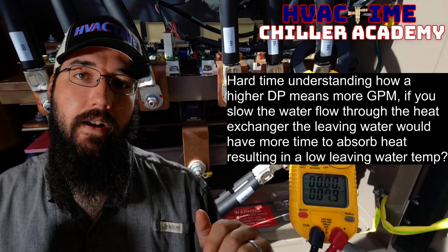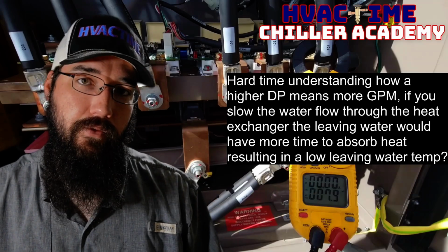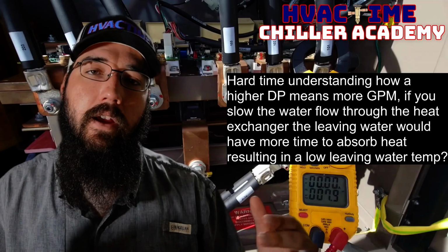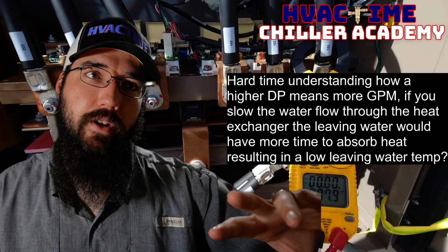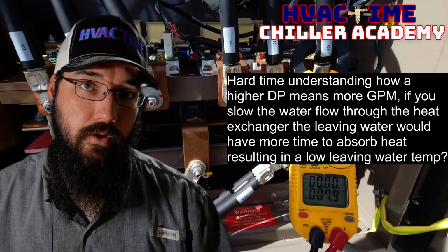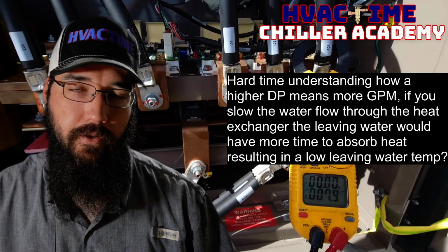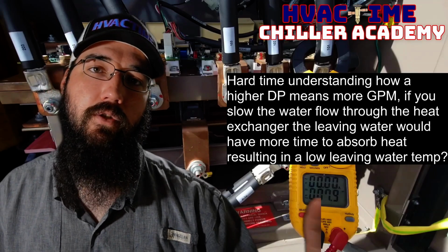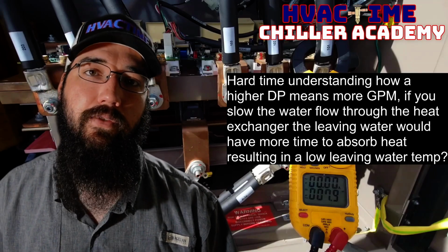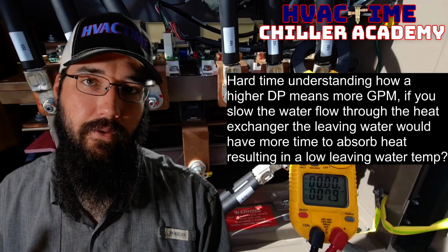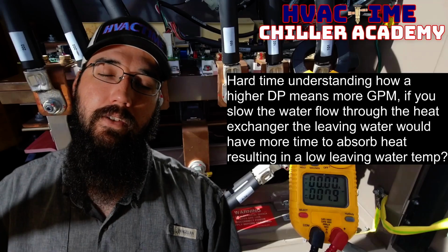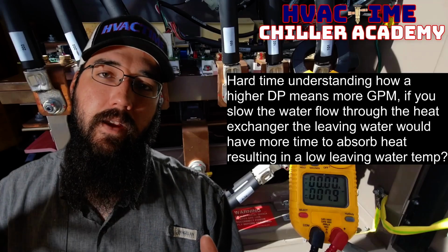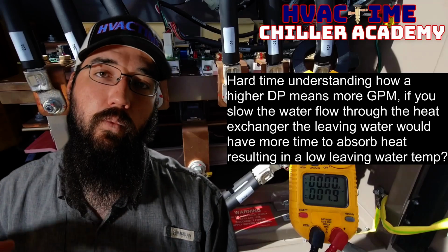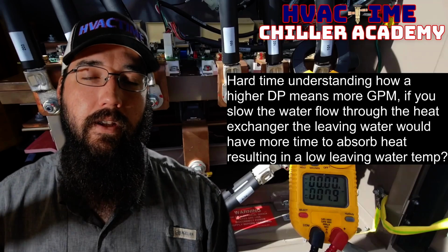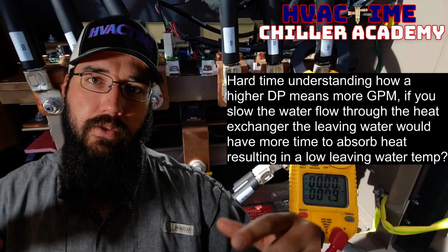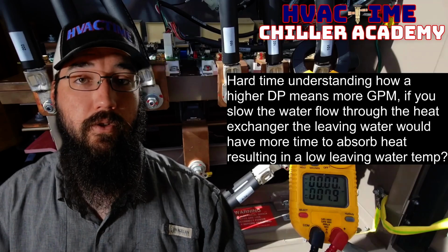So getting back to the pressure side of this, there is a difference between how we rate a heat exchanger and how we rate, say, a valve or like a balancing valve. So with a valve, if we create a pressure differential across there, or a strainer is another example of this, the more differential across that component, the less flow that component is actually letting through it. Whereas with a heat exchanger, if we want more flow, we're trying to increase the differential. More flow does reduce the temperature difference across there.